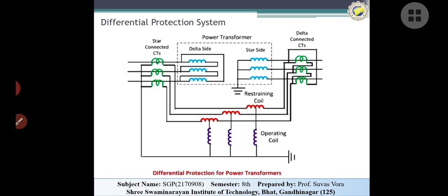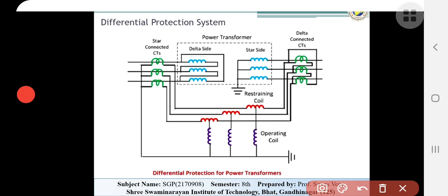In the last lecture we saw how it works. The differential protection system is generally like this: these are the internal circuits of the transformer, this one is the input side and this one is the output side. This coil is called the restraining coil and this coil is called the operating coil. So the restraining coil and the operating coil are summations of all the values.